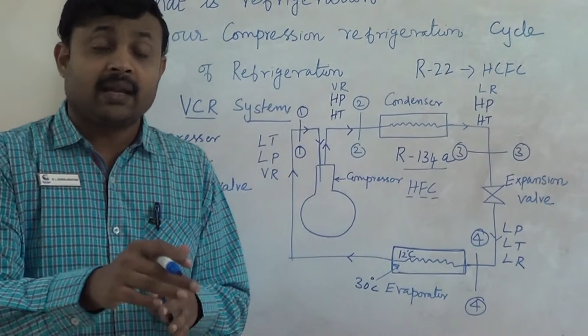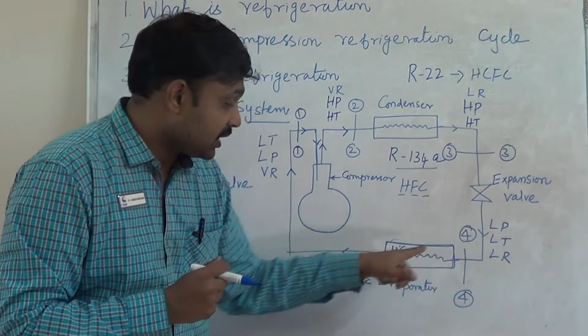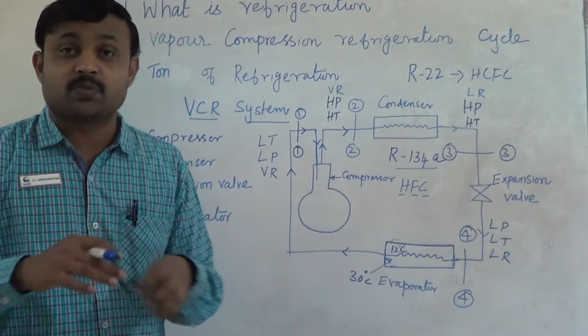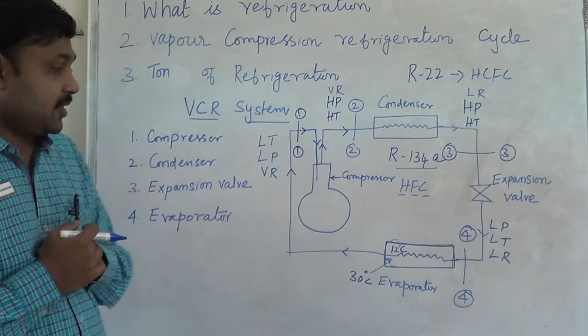So that is what this low temperature, low pressure, liquid refrigerant does: as it passes through the coils of the evaporator, it absorbs the heat from the products that are kept inside the refrigerator. Once it absorbs, since it is an evaporator, evaporation takes place and the refrigerant, being a low boiling point fluid, even when it absorbs the heat from the products inside the refrigerator, the liquid refrigerant is converted into vapor refrigerant. Once the heat is absorbed inside the space, automatically the cooling effect will be produced inside the refrigerator.